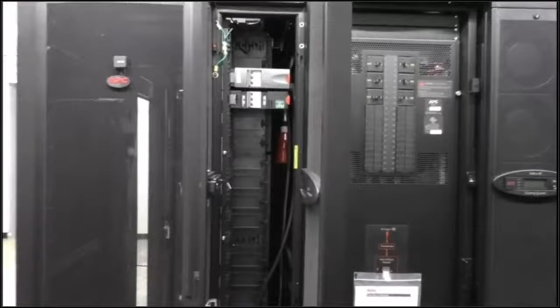This is one of the advances in modular distribution, where the breaker and whip assembly are all in one system. This system goes through this distribution center, up into the above-the-rack area, and into a UL-rated distribution channel. So this cord would be up here and then plug into the plug strips you see here, and those plugs power the equipment. These plug strips are inside each rack, and there's usually two feeds, an A and a B, from separate systems, again to provide an even higher level of reliability.